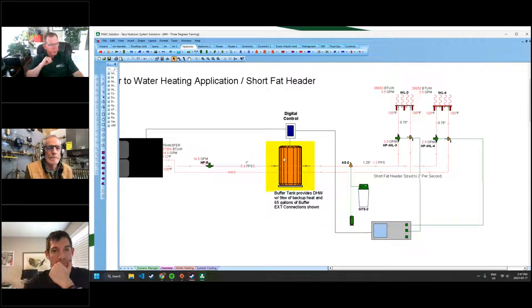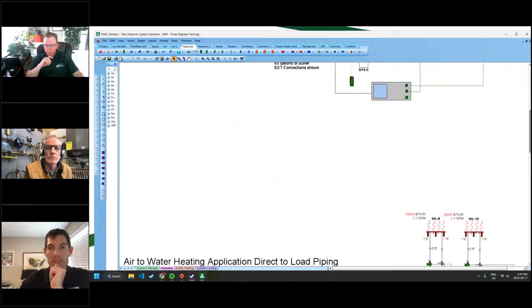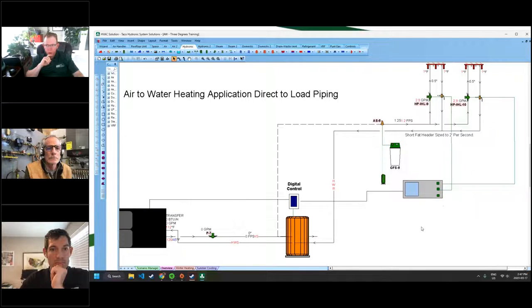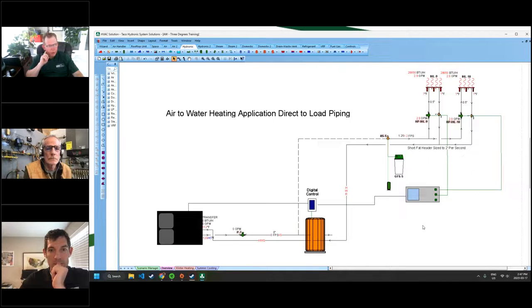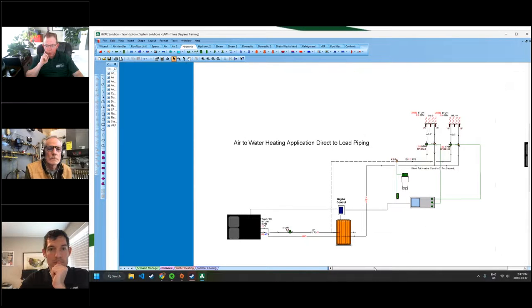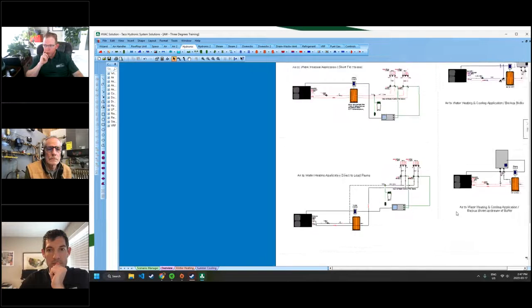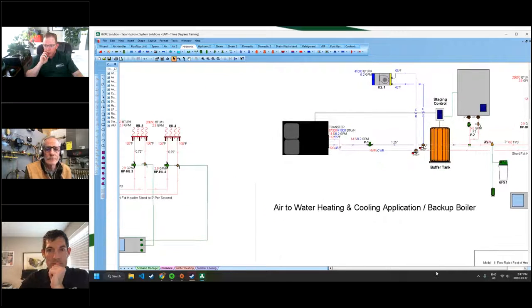This is a very specific buffer tank we've selected for this application, but this is the KISS method. I like that it's simple, it's clean. So whether we do this one or if we simply bypass that buffer tank as shown here, this is another excellent way to do it. And just again, be aware that if you have a cooling load, we want to make sure as we make our way over to our cooling drawing, we have to be very, very sure.